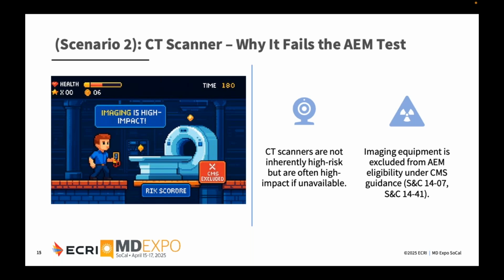Their physicist group, in a large enough healthcare system, has determined on imaging, we need these checks more frequently, but none of them that we've seen, at least from an ECRI standpoint, with that system are PM, not turning a wrench, not opening up something. It's verifying the quality of the image. Does that make sense? So yeah, I would put it in your MEMP or in your AEM. Any other thoughts where you would put it? I should have done this, and I apologize for this.